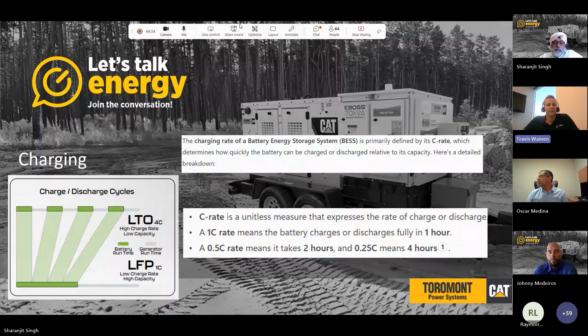Yeah, so this system here, Oscar also mentioned the battery cycle life of this battery. With the LTO battery chemistry, essentially, we get up to around 80,000 cycles on the battery, which means we're kind of building this like maybe a Ford Power Boost pickup, right? The battery size is really small. It's charging and discharging as needed, but it's maintaining the overall efficiency, or making the overall system efficiency higher.